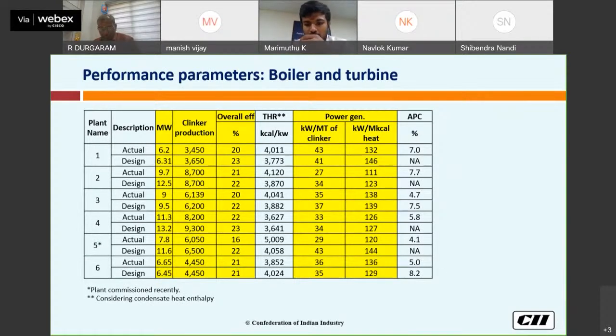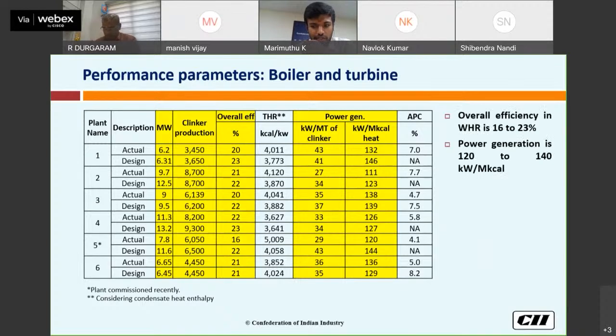Then this table gives figures on boiler and turbine parameters. The overall efficiency of the system for different cement production capacities is illustrated. It is in the range between 16 to 23%, and power generation is around 120 to 140 kilowatt per million kilocalorie, and the turbine heat rate we found is around 3,627 to 4,120. This is a turbine heat rate calculation based on considering the condensate heat enthalpy.